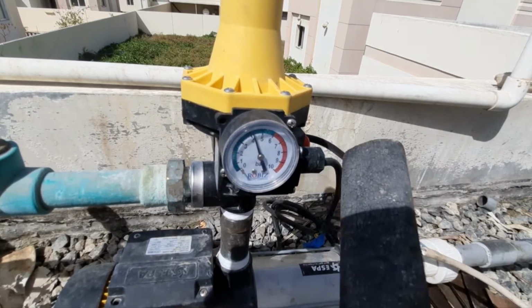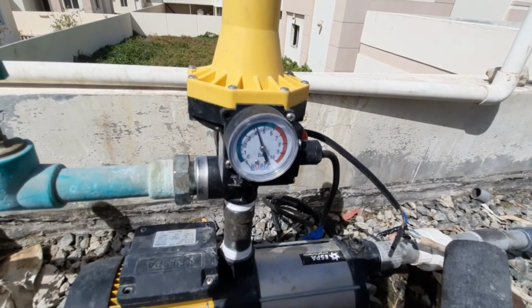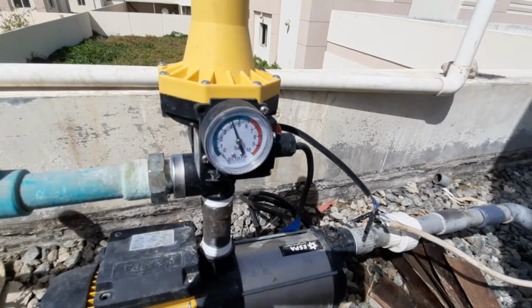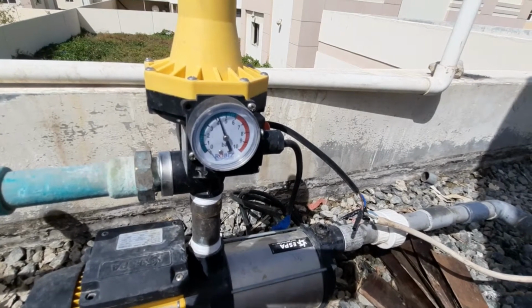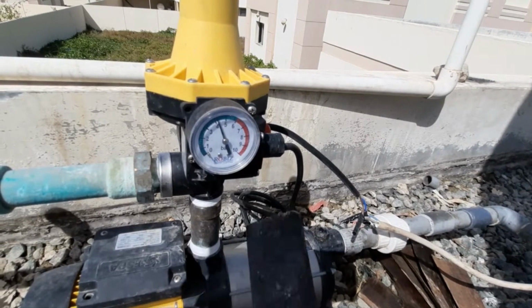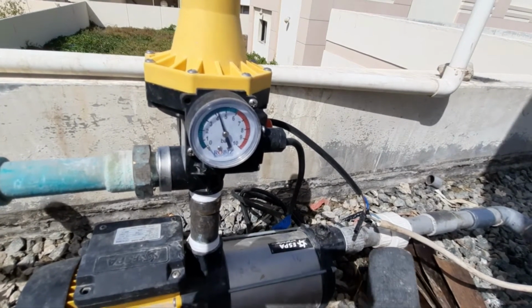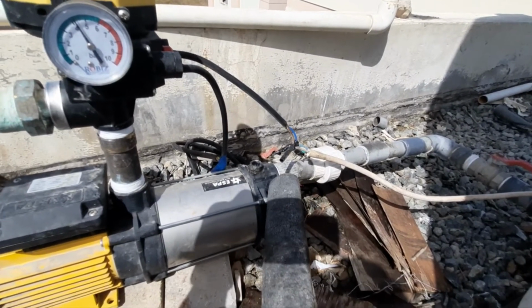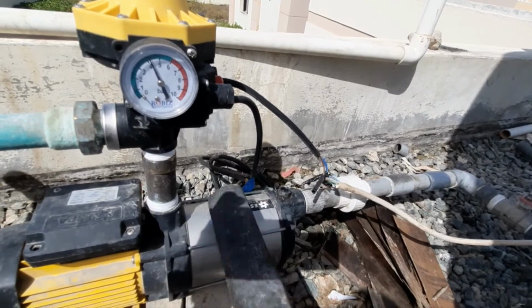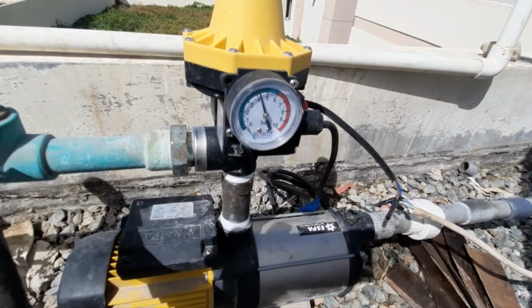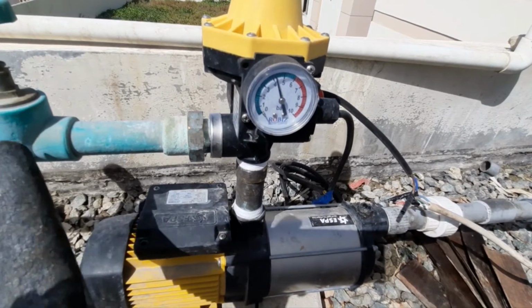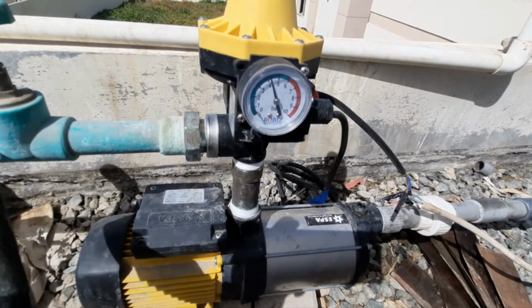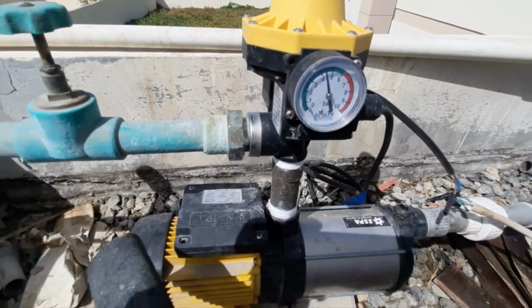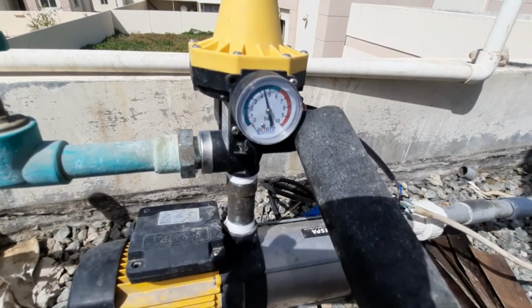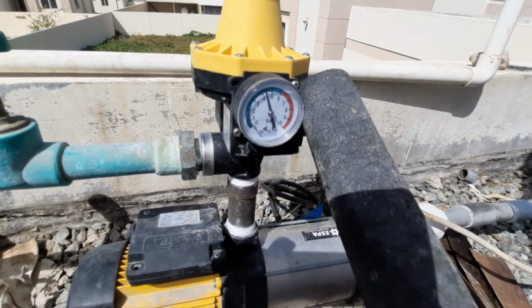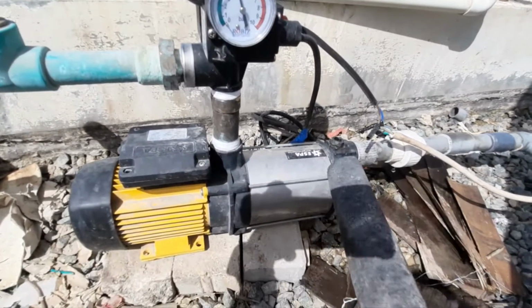So basically the advantage of this pressure switch is you don't need to install a water level switch or safety switch inside the tank, because this is acting double purpose. No supply from the tank or from the city water, the pump will turn off by itself. It will not burn the motor. And if there is no consumption inside the house or the outlet and it builds a pressure, the pump will automatically turn off. So this is acting double purpose and it acts as safety for the motor or for the pump.